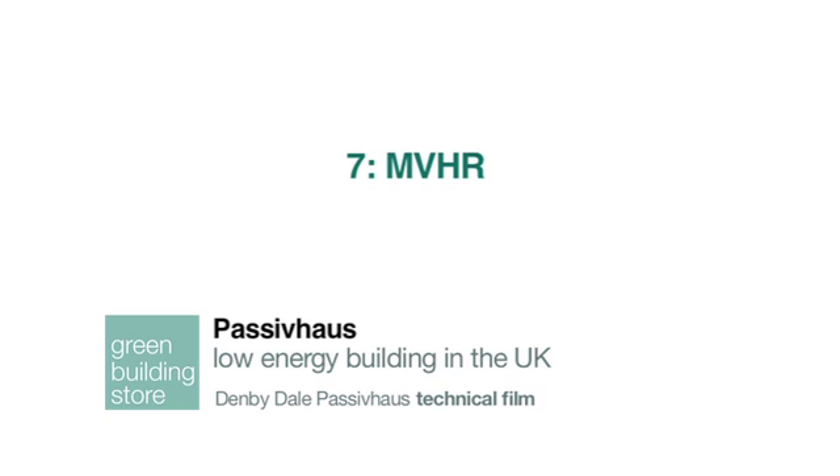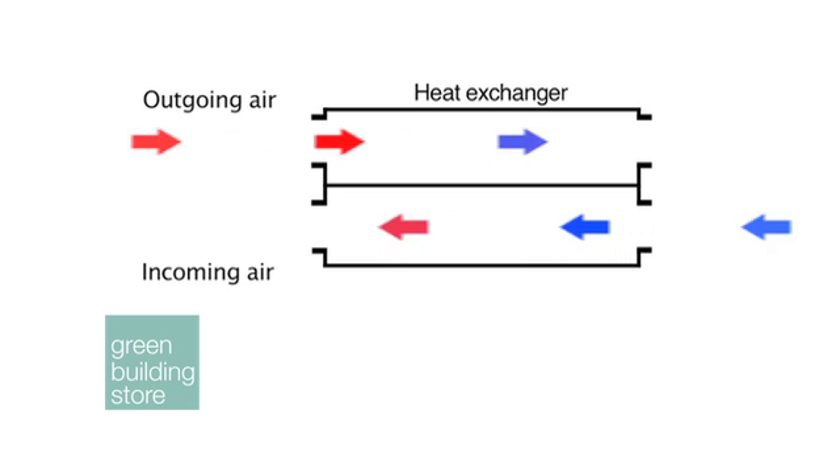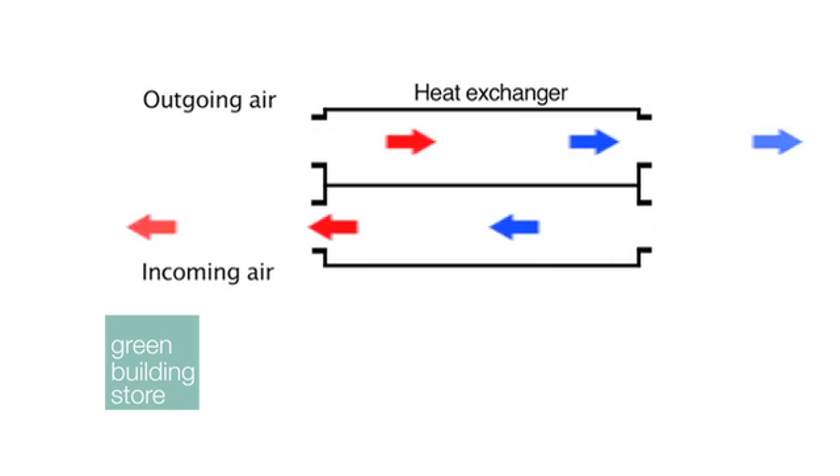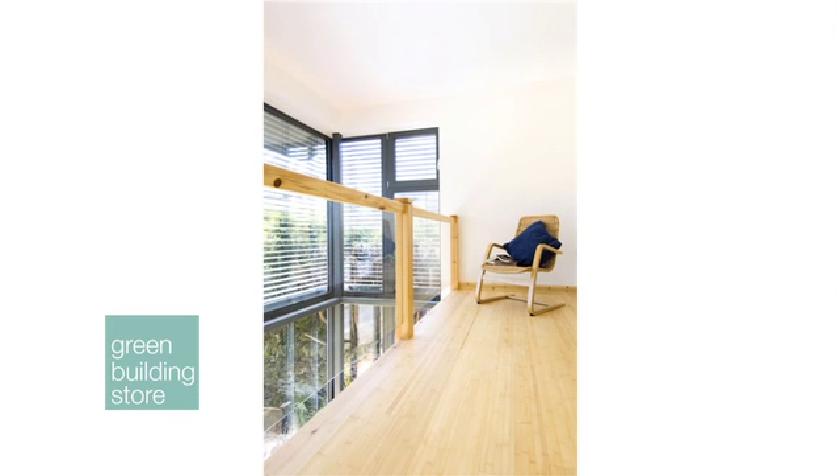Our MVHR unit at Denby Dale will be recovering 92% of the heat generated within the building through solar gain, human activity, electrical goods, and lighting. It does this by passing outgoing air through a heat exchanger past incoming air, transferring the heat but without mixing the stale air with the fresh air.